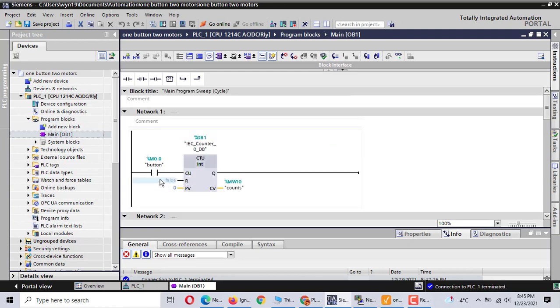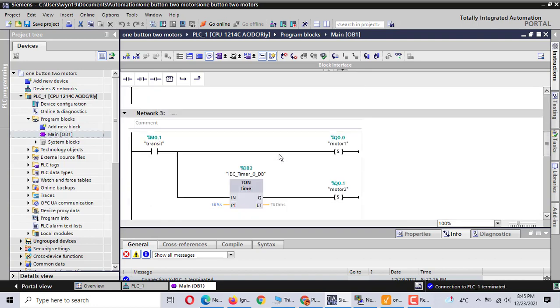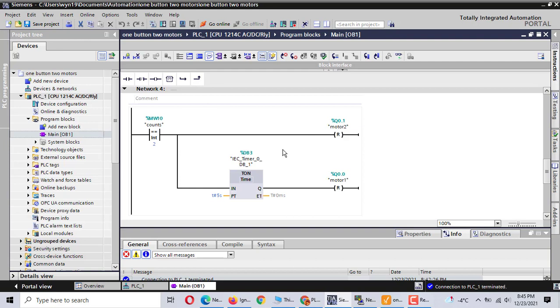Then you push the button again — second time pushing the button, the counter becomes two. If the counter becomes two, the compare instruction checks for two. If it equals two, the compare instruction triggers, and motor two is reset. After five seconds, motor one is reset.